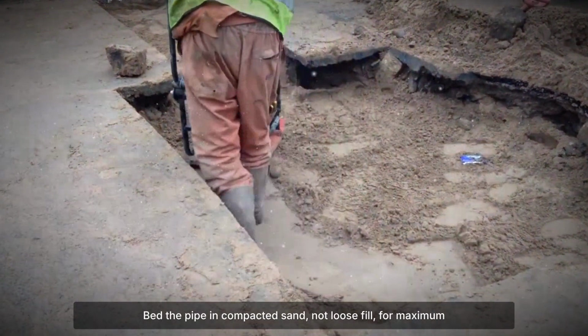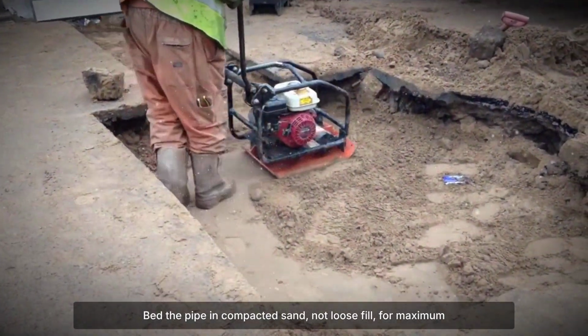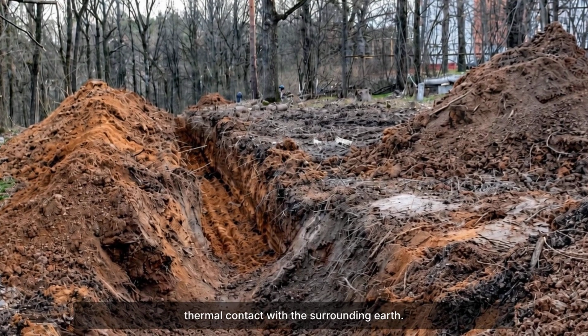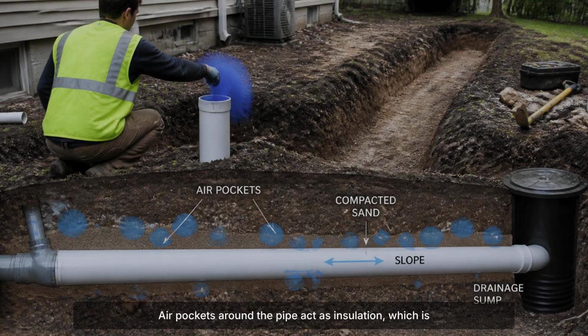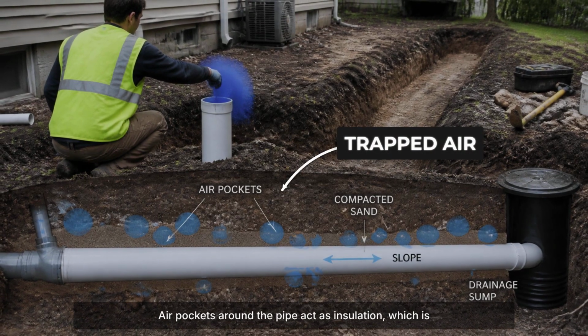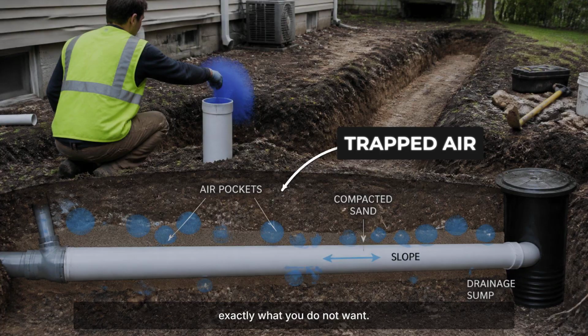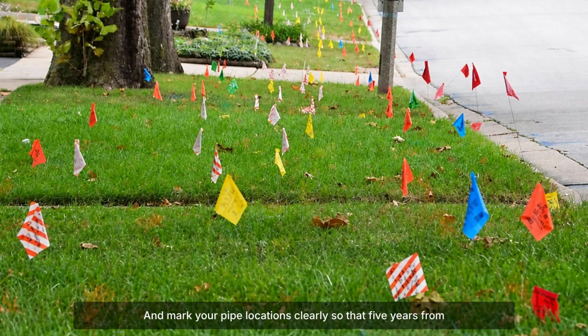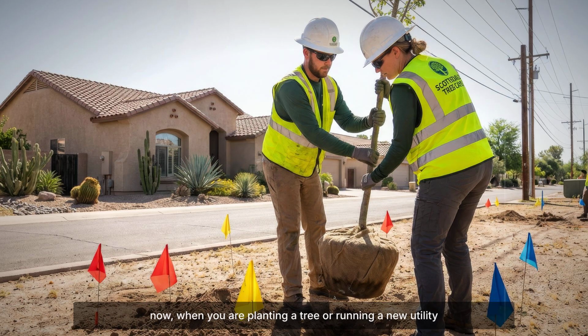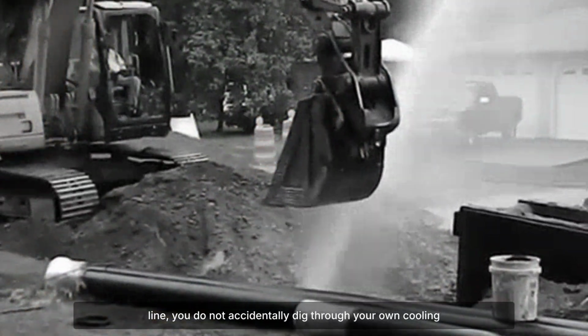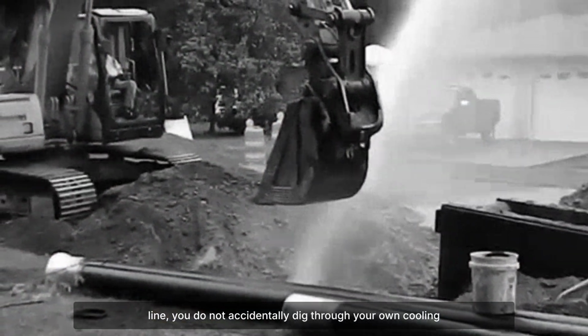Bed the pipe in compacted sand, not loose fill, for maximum thermal contact with the surrounding earth. Air pockets around the pipe act as insulation, which is exactly what you do not want. And mark your pipe locations clearly so that 5 years from now, when you are planting a tree or running a new utility line, you do not accidentally dig through your own cooling system.